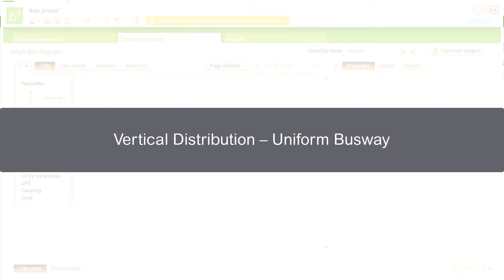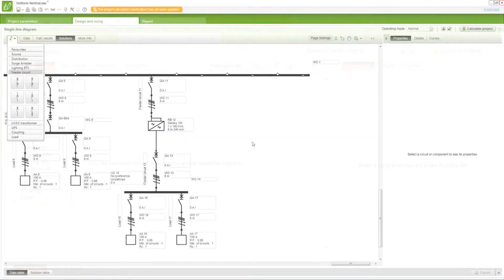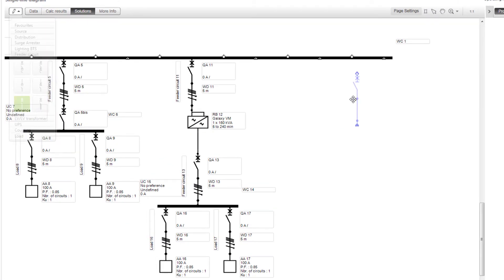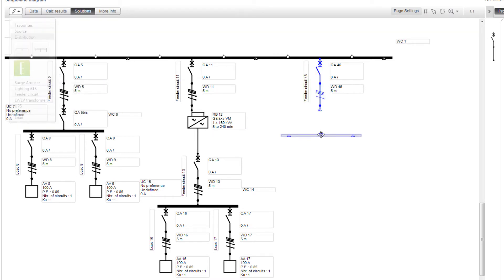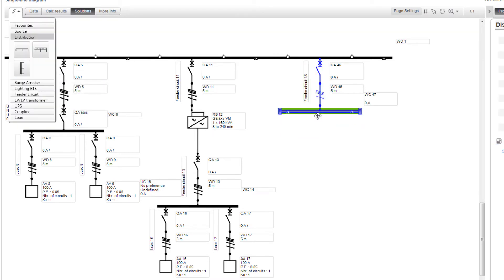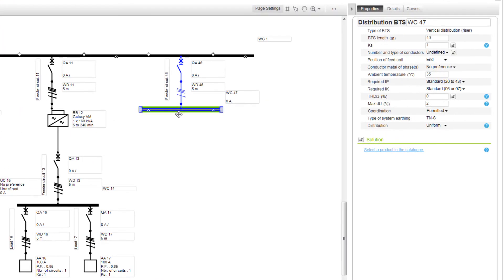Next, we will view how to size a uniform busway for vertical distribution. A vertical distribution busway has to be added to this installation. Ensure that you select a proper feeder circuit which can be connected to the vertical busway. After the feeder circuit is connected, add the vertical BTS riser. The vertical busway can be calculated for uniform or non-uniform tap-off units distribution. We will keep the distribution as uniform.